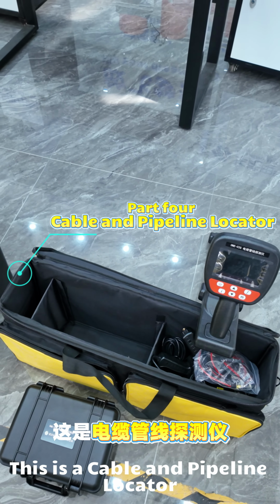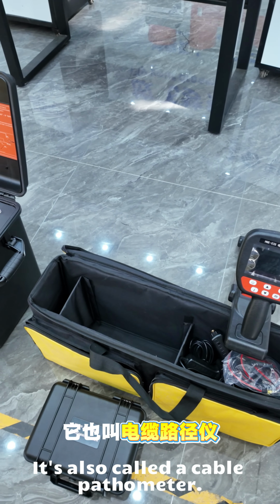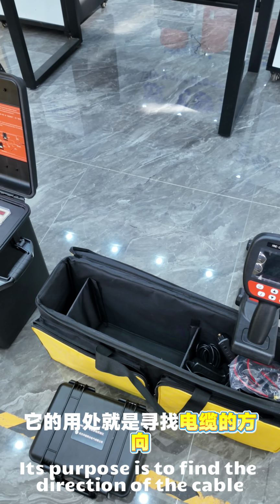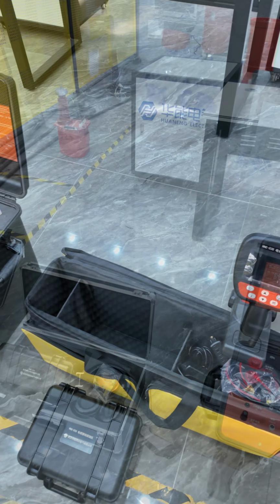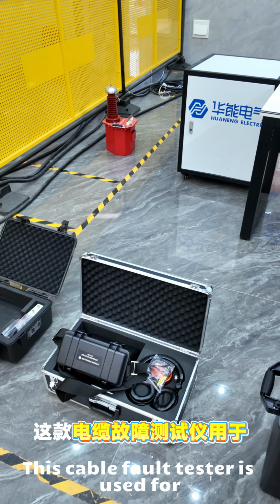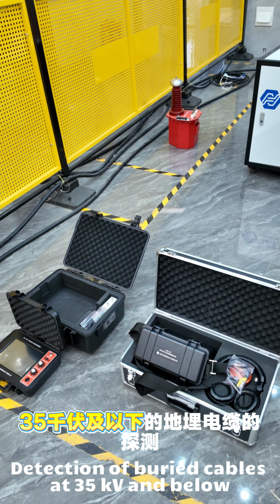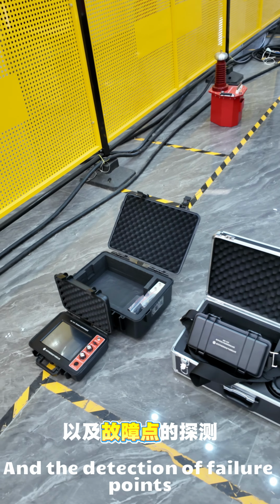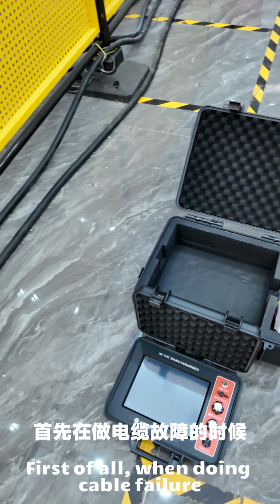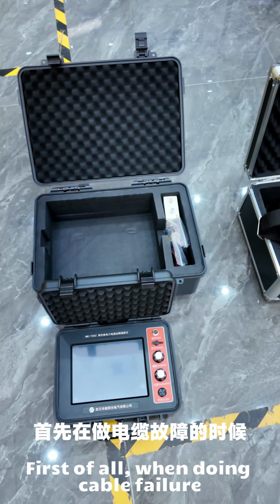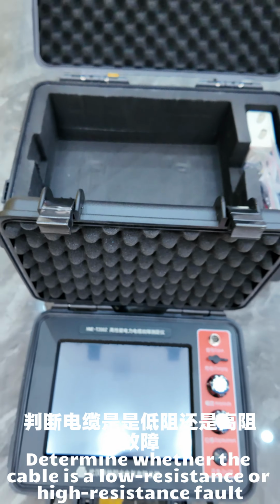This is a cable and pipeline locator. It's also called a cable profiler. Its purpose is to find the direction of the cable. This cable fault tester is used for the detection of buried cables up to 35 kilovolts and the detection of failure points.